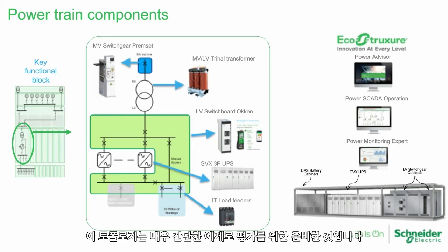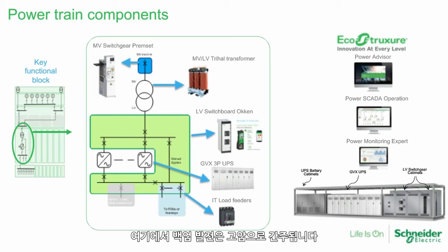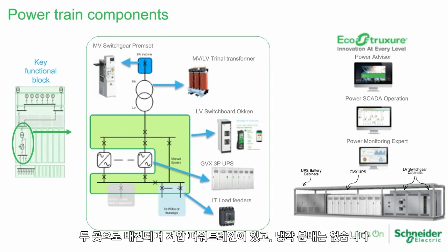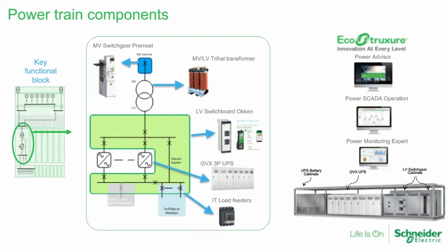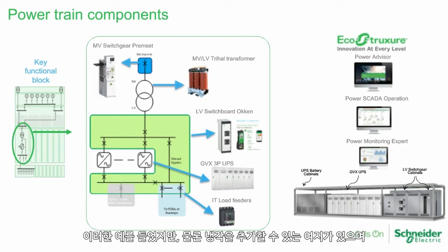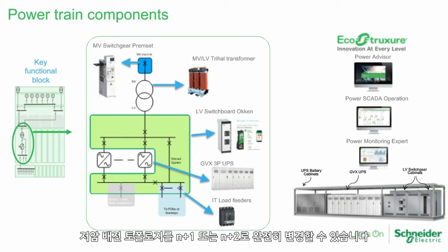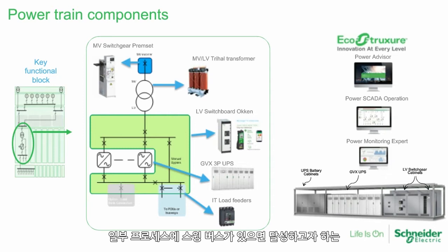It's an assessment for this one. The backup generation is considered at medium voltage. This one considers also a two-end distribution on the low voltage powertrain, and there is no cooling distribution. So I took this example, but of course we have the flexibility to add cooling, to change completely the low voltage distribution topology by N+1 or N+2, having a swing bus with some transfer switch to be able to reduce or to change the type of distribution we would like to achieve.